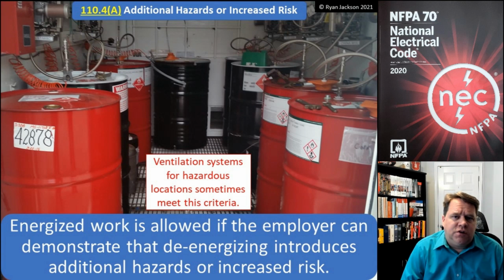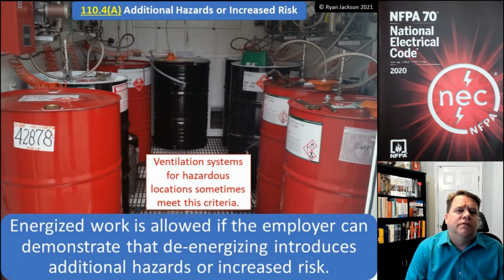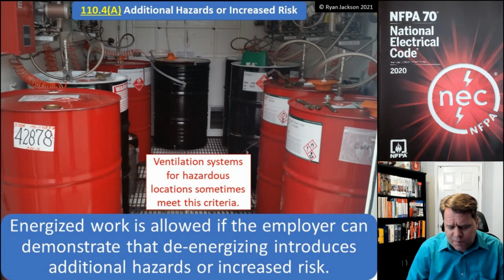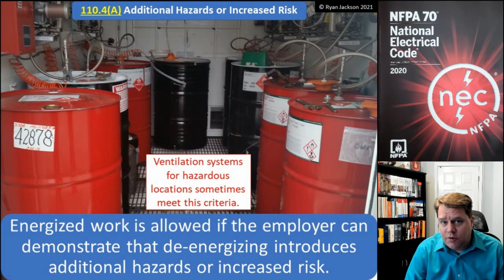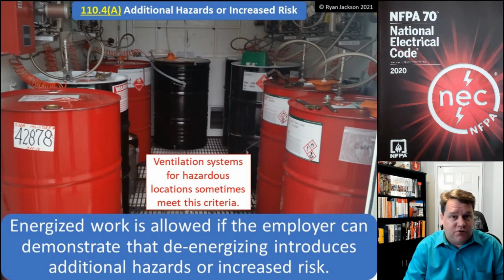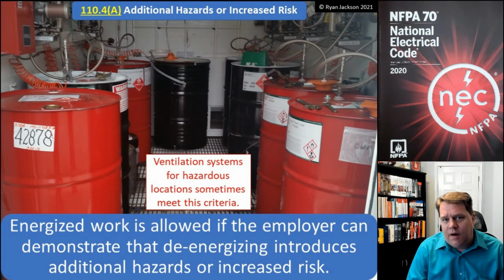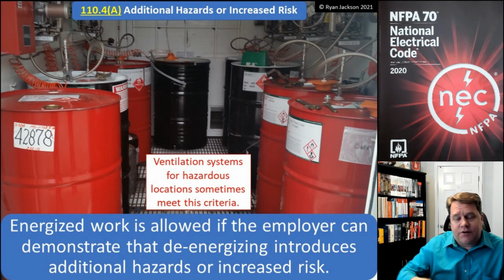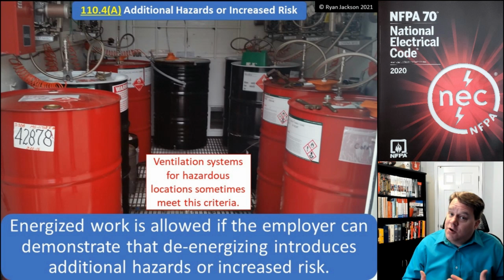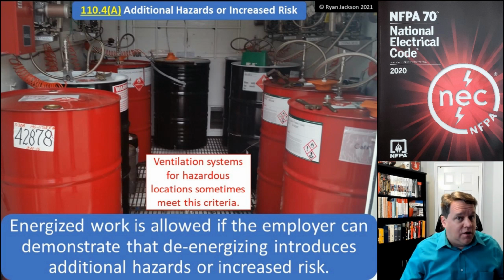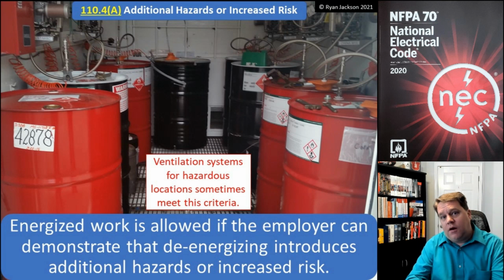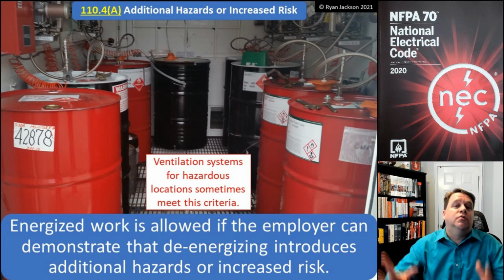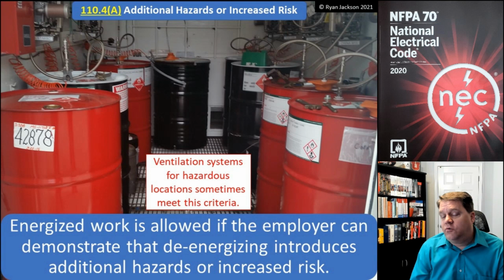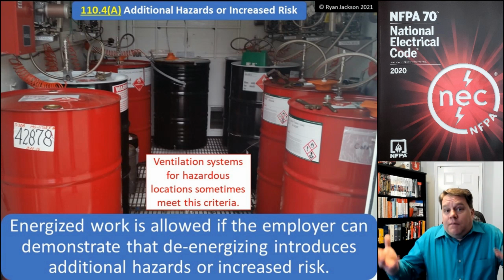Another example that a lot of people choose to use is life support equipment at a hospital. I've talked to a lot of electricians that say, oh, you can't shut off anything at a hospital. And that is simply not true. I know a lot of people that work for hospitals or do electrical work strictly at hospitals, and pretty much none of them agree with that statement. The hospital doesn't want you working energized. If they have patients on life support equipment and the electrician explains to them, listen, I'm a human. I make mistakes. Whether it's my fault or nobody's fault, sometimes bad things happen. If I'm working in this panel and something goes wrong, you're not only going to lose the one circuit that you're worried about with the life support equipment, you might lose the entire panel, or you might lose the entire switchboard or switchgear. And if it's a bad enough incident, it might be permanently damaged.